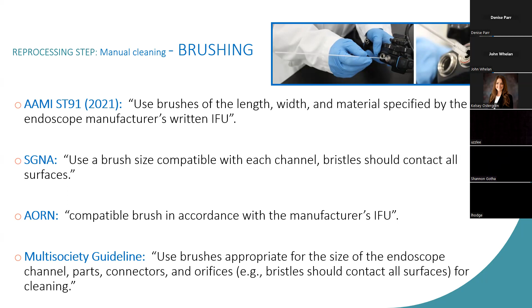AAMI ST91 gives recognition that there are some current generation AERs that have cleaning cycles that are validated and FDA cleared, but the emphasis is that automated cleaning cycles don't replace or abbreviate point of use treatment at the bedside. And if you consider replacing full manual cleaning with automated cleaning, or if you have what they now call modified cleaning at the sink, you as an infection preventionist should be part of a multidisciplinary team to conduct a risk assessment of your entire processes before you sign off on that.